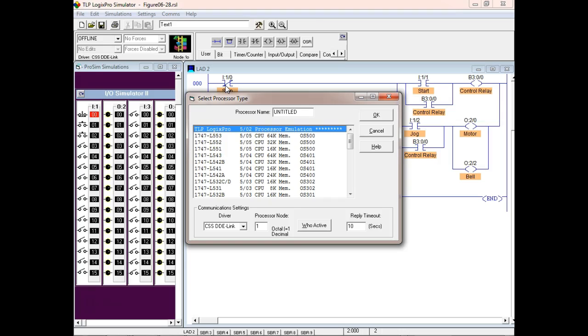So did I say that right? On the fixed PLC, I think I said modular. So on the fixed PLCs, the CPU has no address, so it does not occupy a slot. And also on the fixed PLCs, especially on the MicroLogix, your I/O ports start at 0. Your input ports are considered slot 0, and your output ports are considered slot 0 because there's no slots, right?